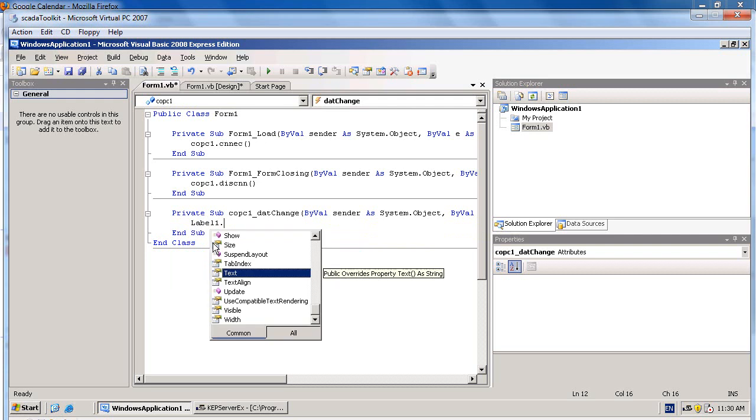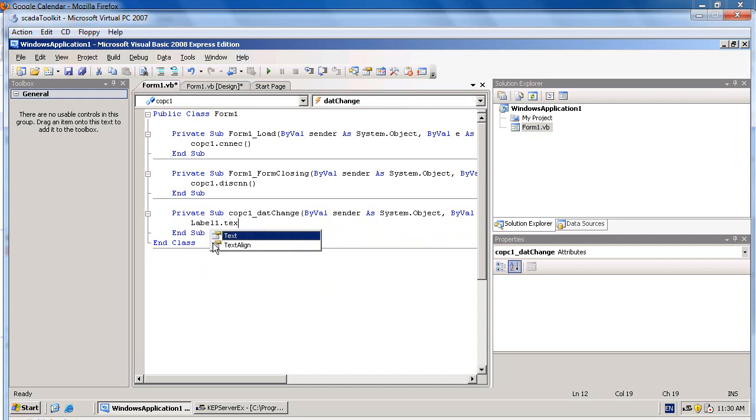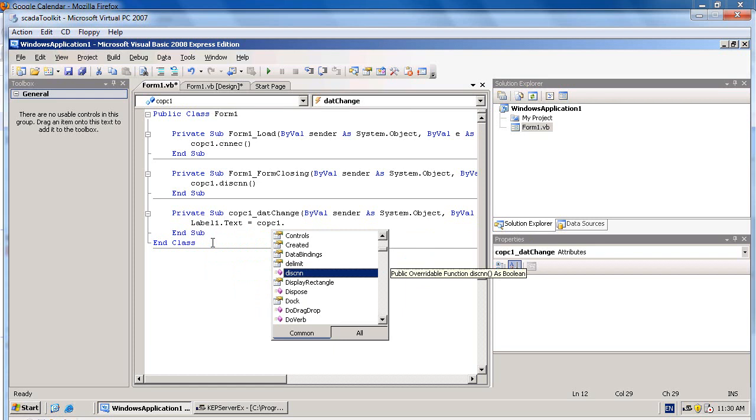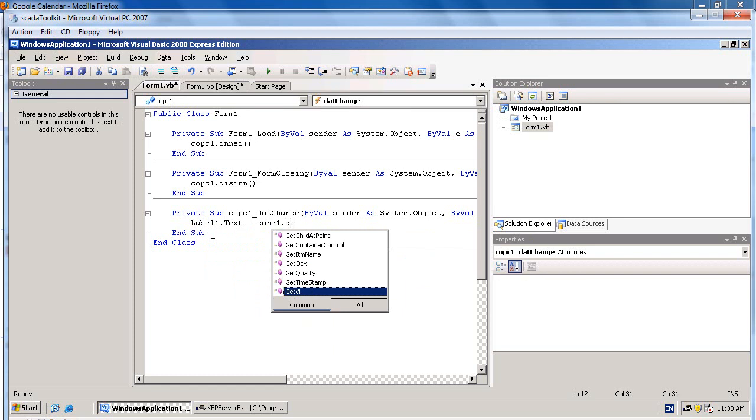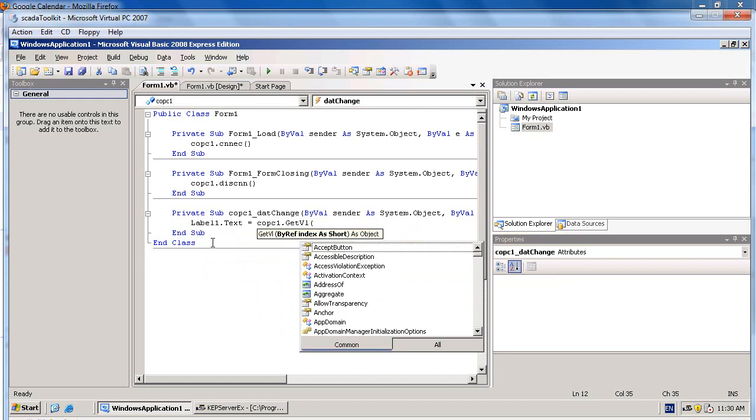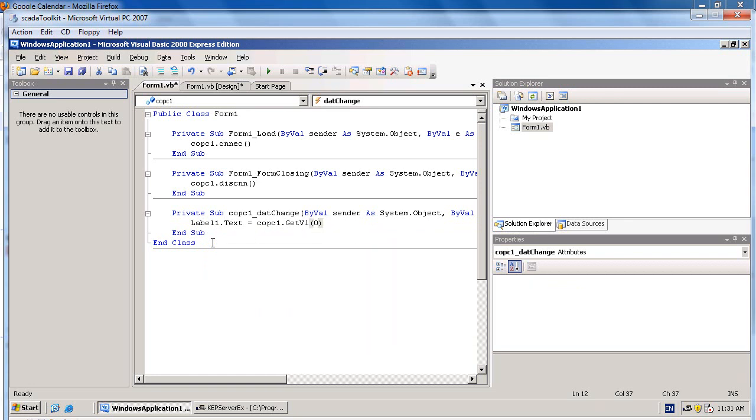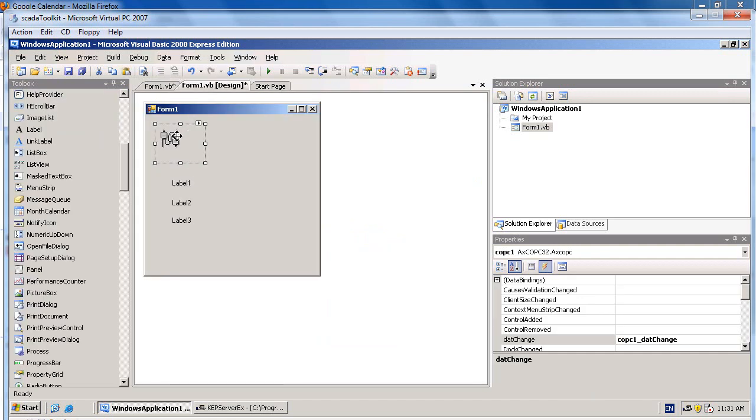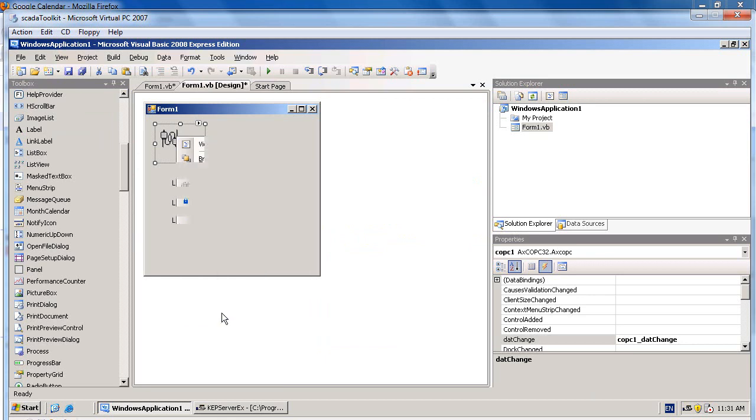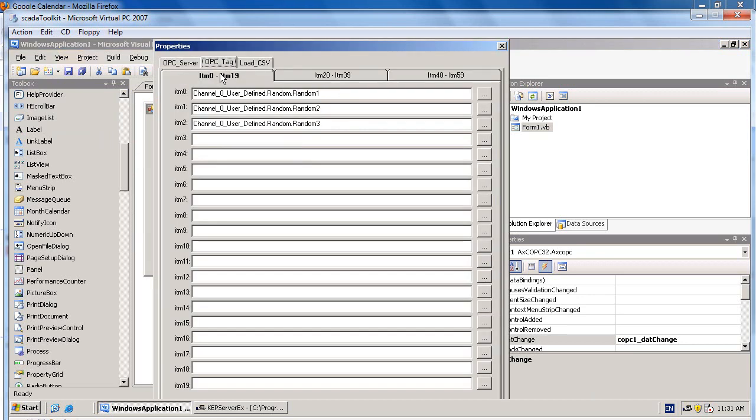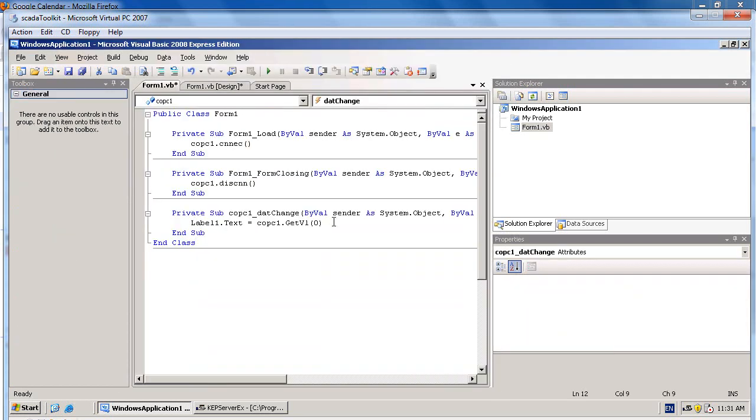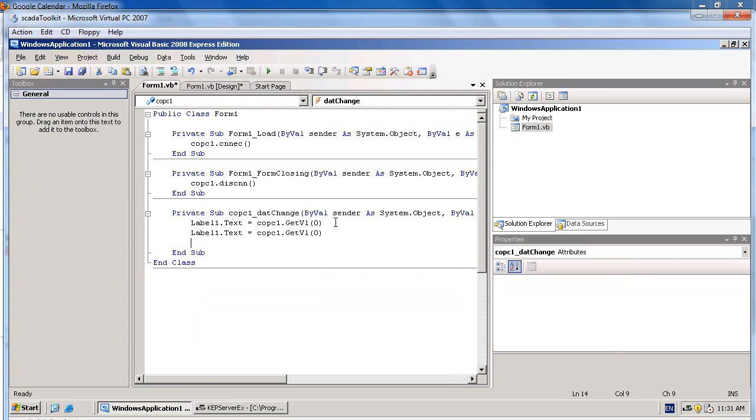Label1.Text equals COPC1.GetVL. GetVL is the method to get the value of OPC tags. You need to specify the index number of the OPC tags. If you cannot remember, get back and go to the property of COPC control. You will see the index number of each OPC tag. Similarly add the second and third labels.